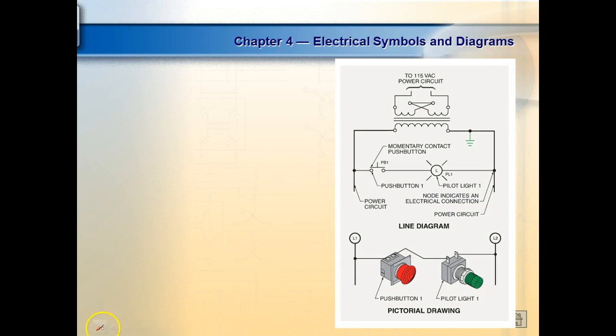So if these are labeled, this would be H1, this would be H2, this would be H3, this would be H4. Over here this would be X1, and this would be X2. On our transformer, it has a fuse built into it, and they refer to this as XF. So XF we're going to use for CL1, and X2 we're going to use for CL2 — control L1 and control L2.